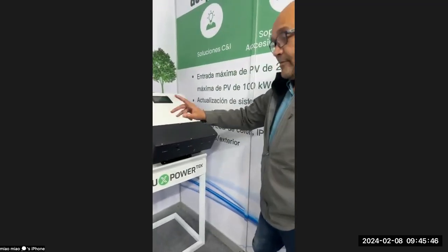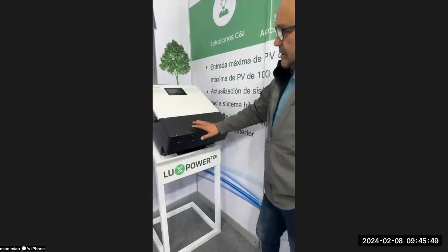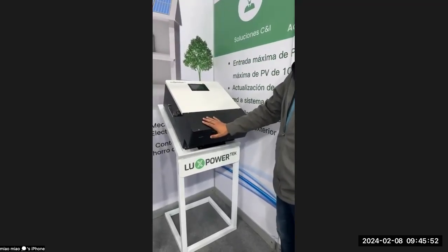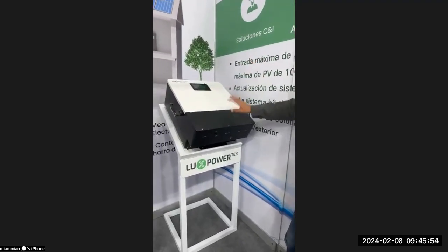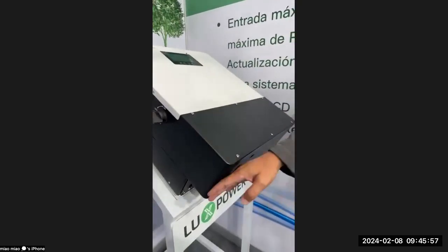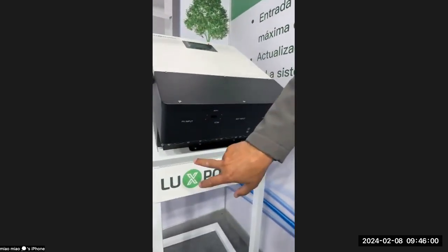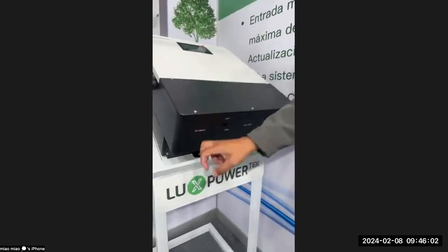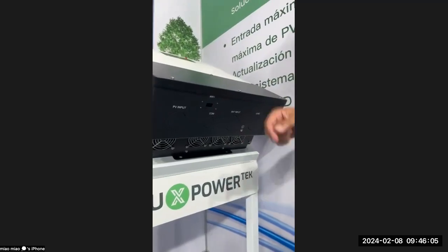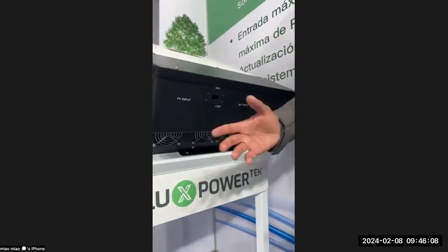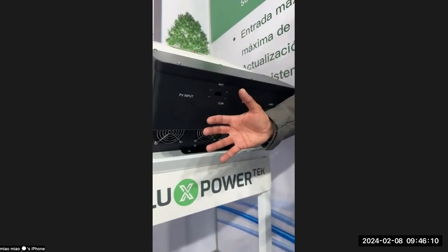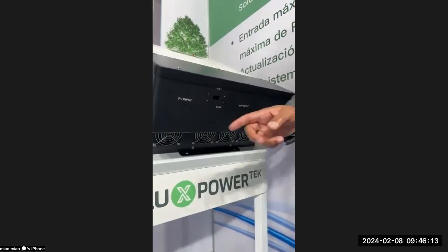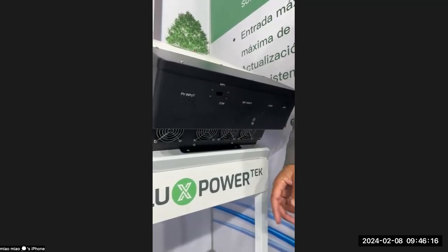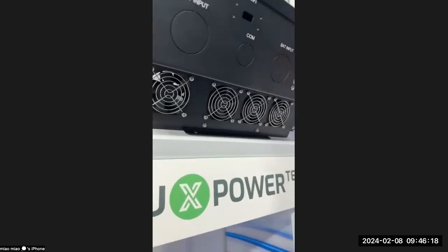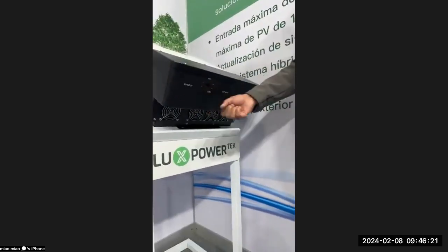So with the 10 kilowatts, many of you have installed this one already, and the 12. We can talk about the external pressed aluminium cover, pressed aluminium chassis. There is no mild steel in this machine. The machine comes with knockouts at the bottom, and we supply all of the glands that go in here. Every knockout that you see has a gland in the box. They're all bundled in a pack, bubble wrapped. So if glands are missing, it simply means that somebody's lost them, but it's definitely not us. Right. So here your cables will feed through the glands.